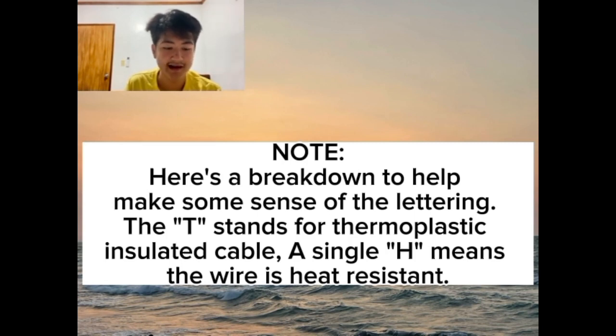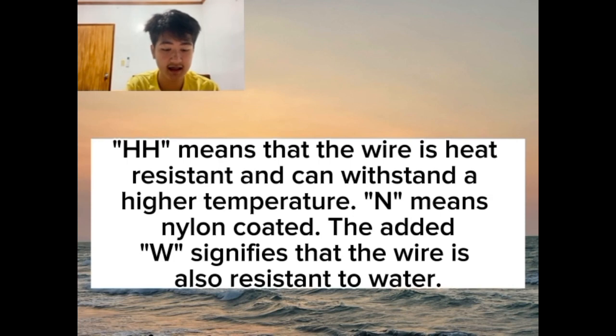So note, here's a breakdown to help make some sense of the lettering. The T stands for thermoplastic insulated cable. Next is the single H. It means the wire is heat resistant. And then the double H, or HH, means that the wire is heat resistant and can withstand a higher temperature. Next is the letter N. It means that it's nylon coated. And then the added W signifies that the wire is also resistant to water.